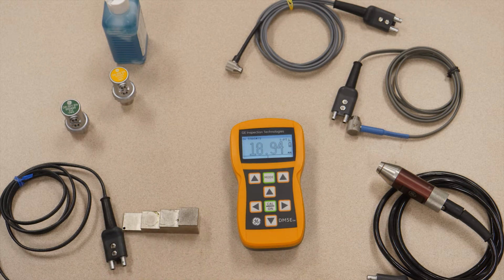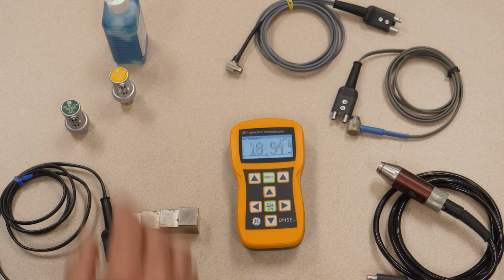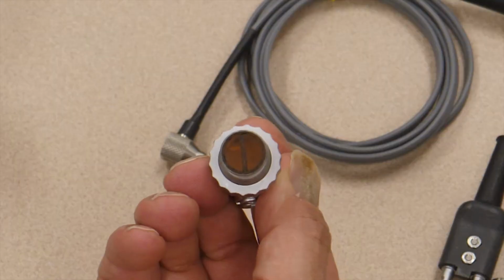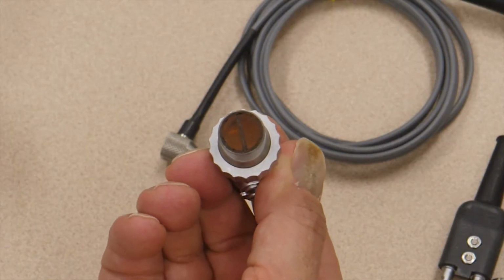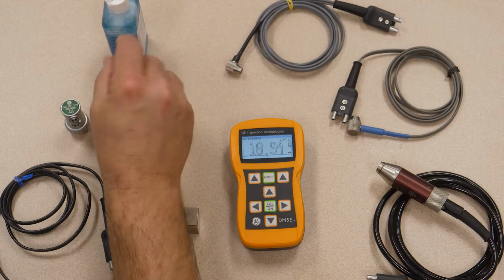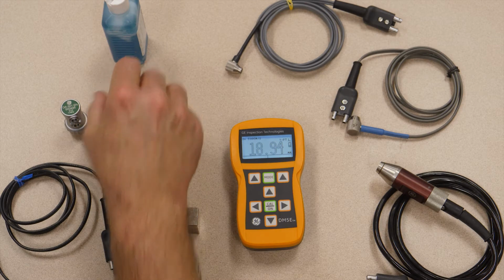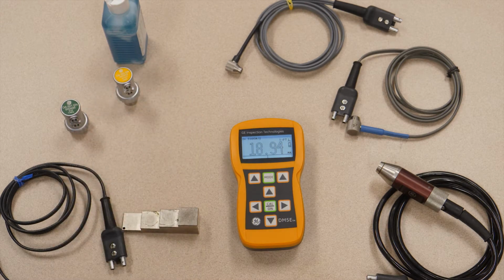This instrument uses only dual element probes. You may be familiar with the dual element probes. Pulse on one side, listen on the other, measure the time that it takes the sound to move through the part, and you can turn that into a thickness measurement. Shown with the instrument here are some of the most common probes.